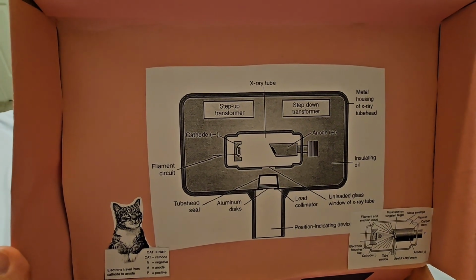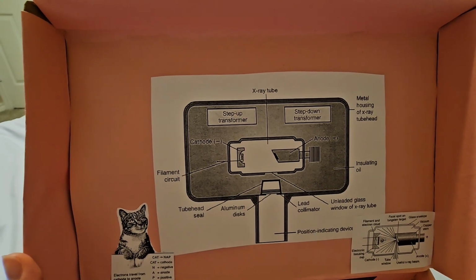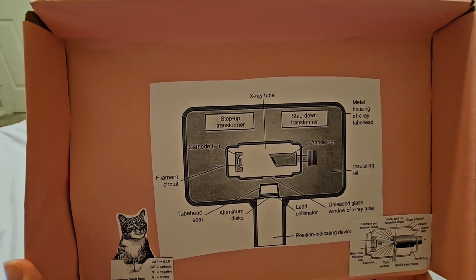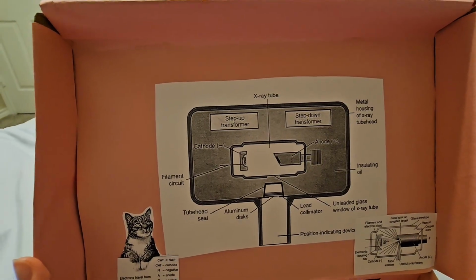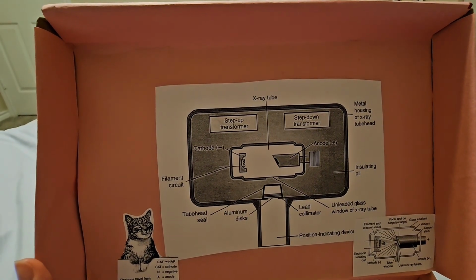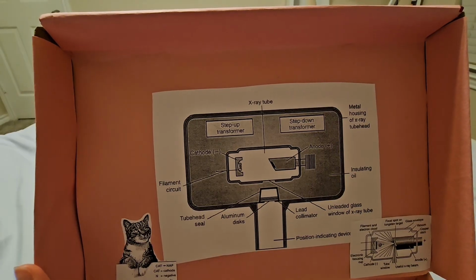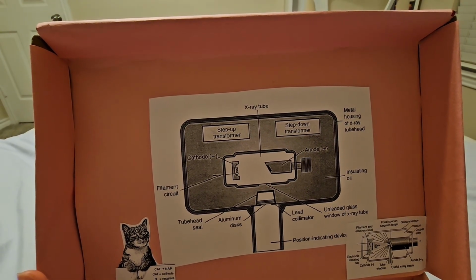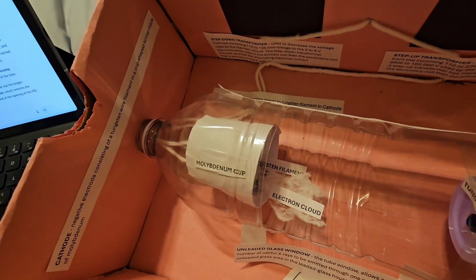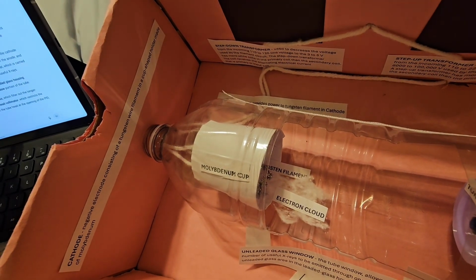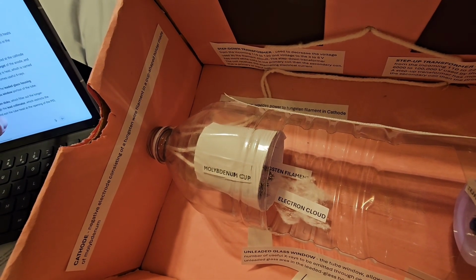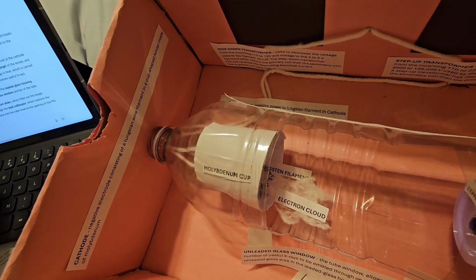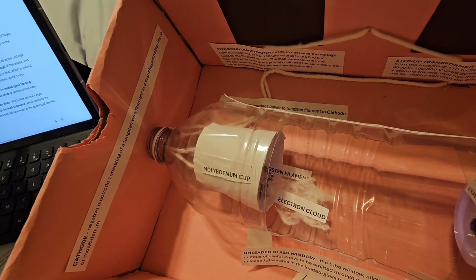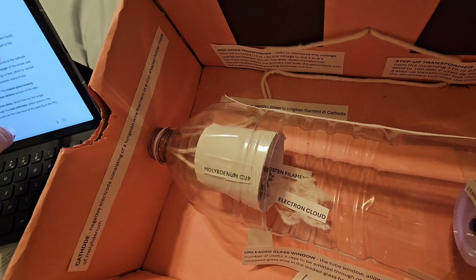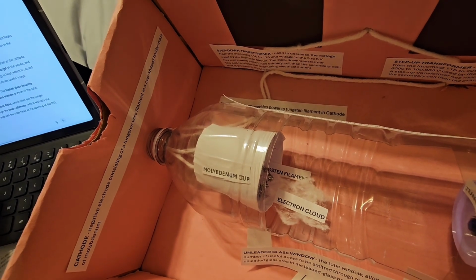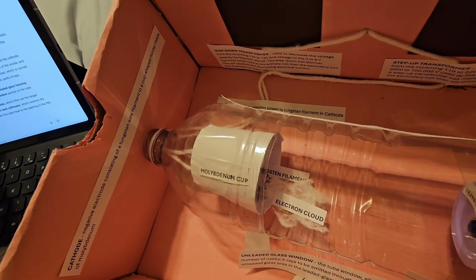X-rays are produced when electricity from the wall outlet supplies power through the control panel to the tube head. Inside the tube head, the current is directed to the filament circuit and the step-down transformer, which reduces the voltage from 110 or 220 volts down to 3 to 5 volts. The filament circuit uses this low voltage to heat the tungsten filament in the cathode. As the filament heats up, electrons are released and form an electron cloud around the filament. These electrons remain in the cloud until the high voltage circuit is activated.